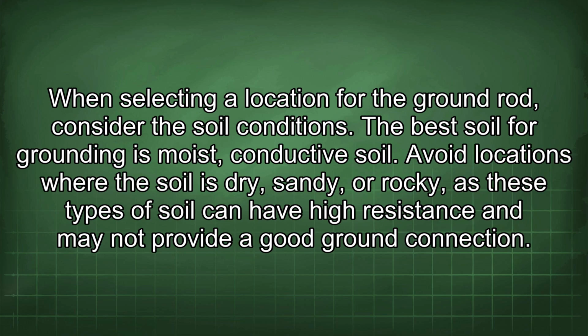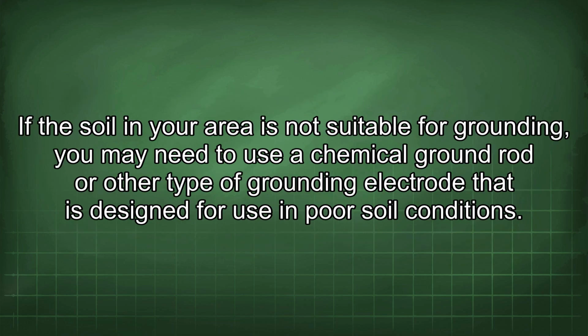The best soil for grounding is moist, conductive soil. Avoid locations where the soil is dry, sandy, or rocky, as these types of soil can have high resistance and may not provide a good ground connection. If the soil in your area is not suitable for grounding, you may need to use a chemical ground rod or other type of grounding electrode that is designed for use in poor soil conditions.